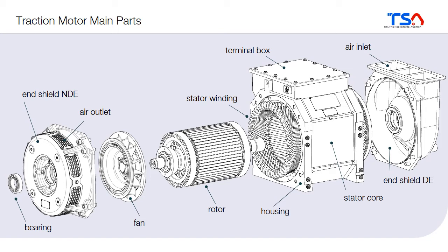Typically there is a stator, which is the non-rotating part. The stator consists of the stator core, which is basically made of iron sheets — there is a lamination, and many iron sheets put together form the stator core. Also in the stator there is the stator winding. You can see the winding heads, but they go through the stator core and then go back. Through the stator winding the current will flow. This is the non-rotating part of the machine, together with the end shields on both sides.